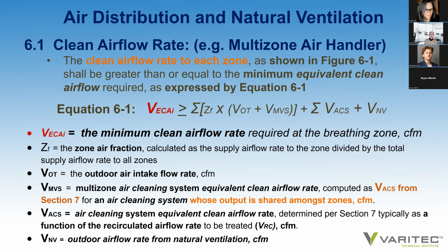supplied by a multi-zone air handler is based on the summation of all the zones' impact, and each zone will involve a calculation of the air zone fraction rate to the zone, the amount of outside air that will be delivered to the zone, and the air cleaning system equivalent clean airflow rate from the air handler itself for a multi-zone unit serving all the zones.